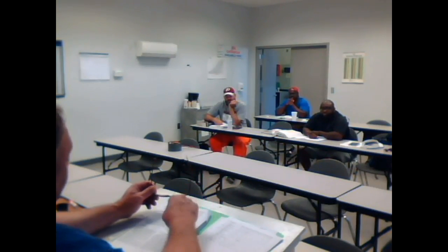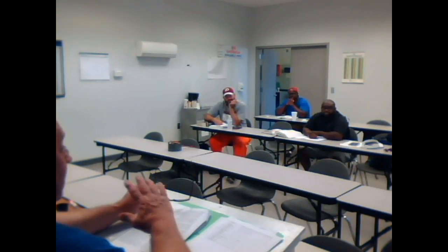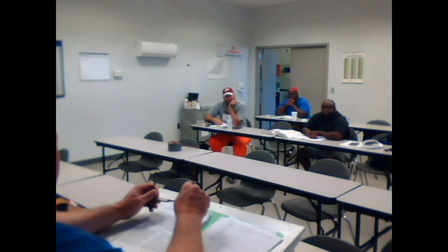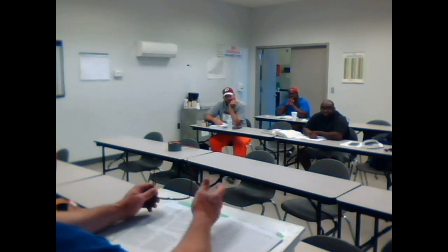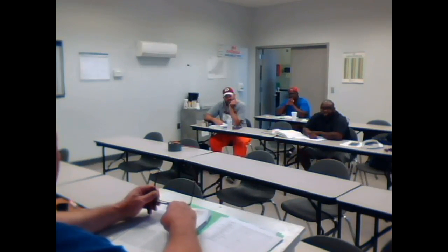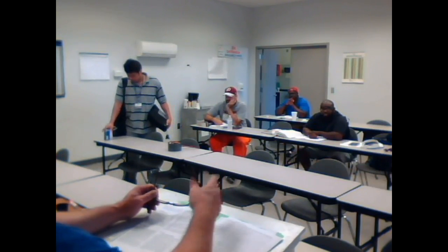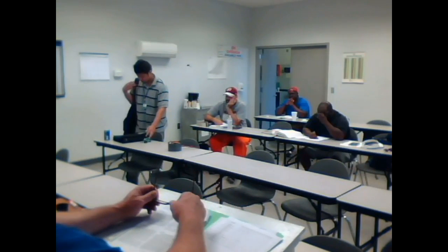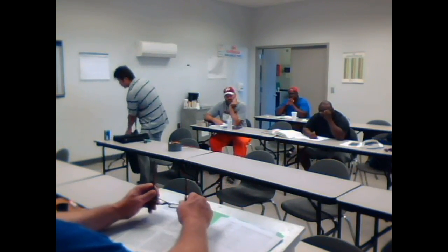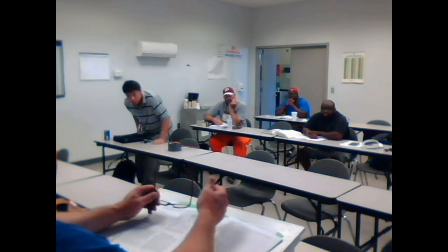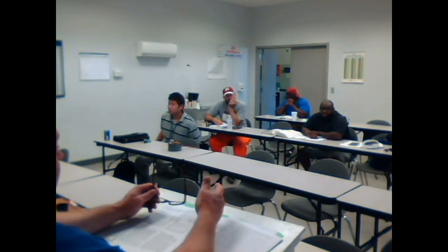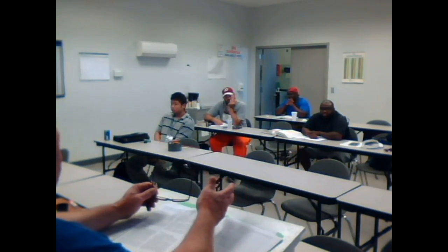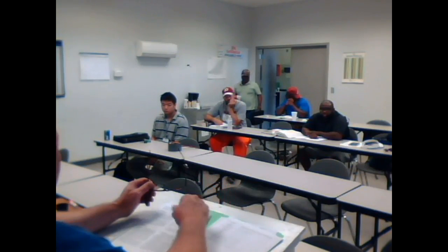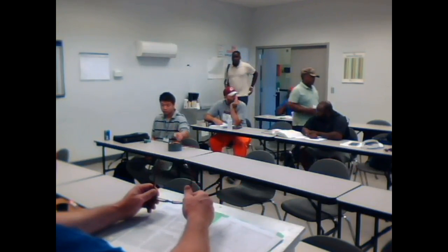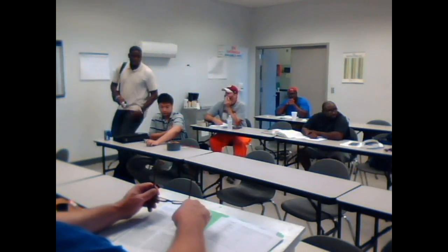But you want to figure out what it is that's wrong, and these are all electrical problems right now. And you're going to write down what you think the problem is and why. If you say bad transformer, well, why do you think it's a bad transformer? Because I ohmed out the coil, primary coil, OL, or maybe it's the secondary, that kind of thing. Say I've got a contactor that you think is bad. Why? Coil's bad, or maybe the contact's bad. I don't know. Unit doesn't have proper voltage. What did it have? What were your readings? Okay? So that's how we're going to handle these labs.